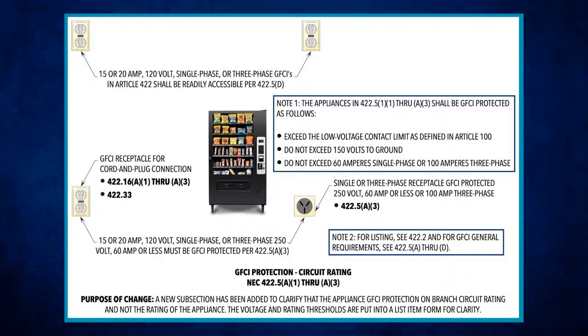It can be within the branch circuit overcurrent device, so at the panel board. It can be a device or outlet within the supply circuit. That's interesting because I've never heard of an outlet that actually provided GFCI protection - I've heard of devices that do. Then it says an integral part of the attachment plug, or it can be within the supply cord, not more than 12 inches from the attachment plug. And then this is the one you want to use, Bill - factory installed within the appliance. Yeah, 100%.